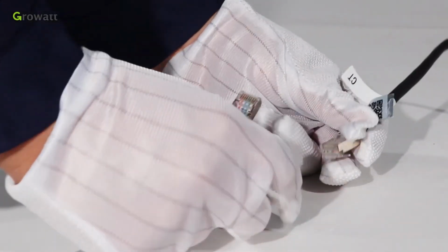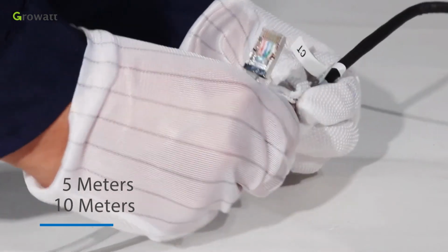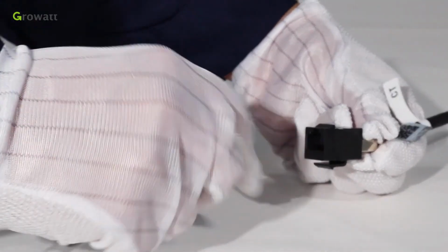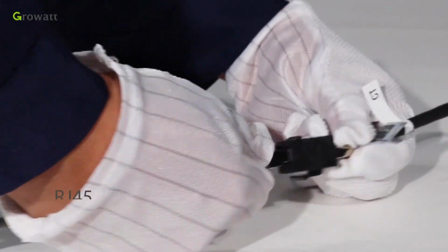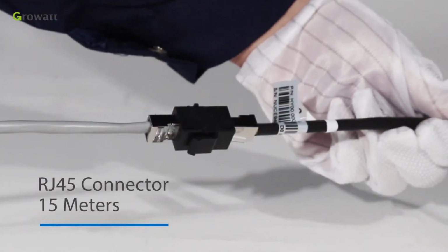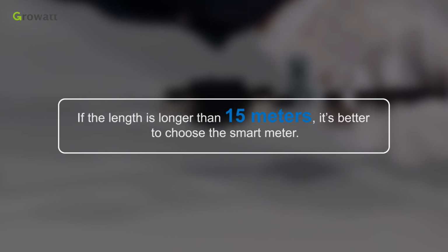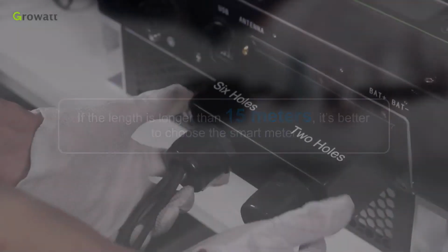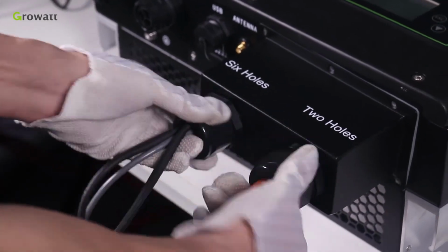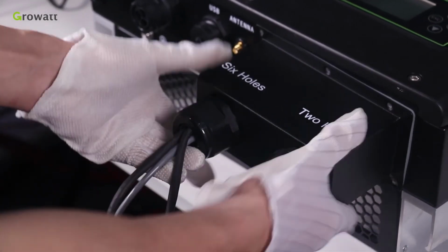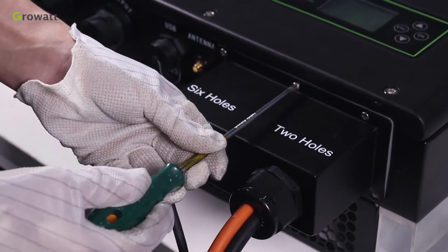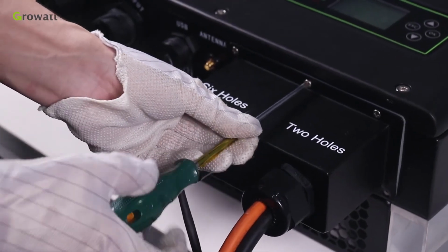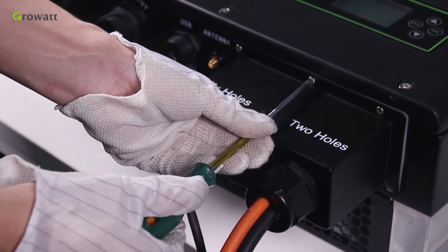Growatt provides 2 cables whose lengths are 5 meters and 10 meters. Growatt also provides an RJ45 connector, so the total length can reach 15 meters. If the length is longer than 15 meters, it's better to choose the smart meter. When all the communication lines are installed, push the waterproof cover into the bottom, lock the screws fixed to the frame, and finally lock the waterproof cap.